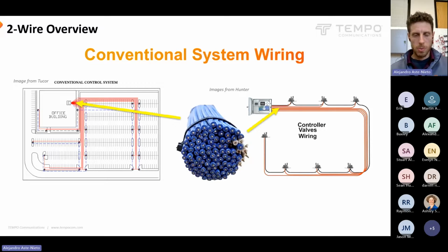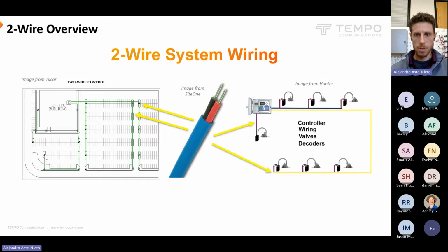So just to compare the wiring coming from a conventional controller and a 2-wire one. As you can see here, in a conventional system, tons of wires come from the controller, one for every single valve out in the field. So the more valves out there, obviously, the more wire. If you compare that with a 2-wire system, a lot less wire is required, especially when there's a lot of valves. You can operate hundreds of valves from one controller in a 2-wire system, and they can all use the same wire path. Usually you'll want to break things up into multiple wire paths, but you can connect a lot of valves just on one wire path.